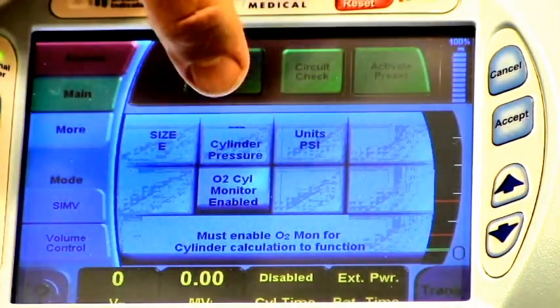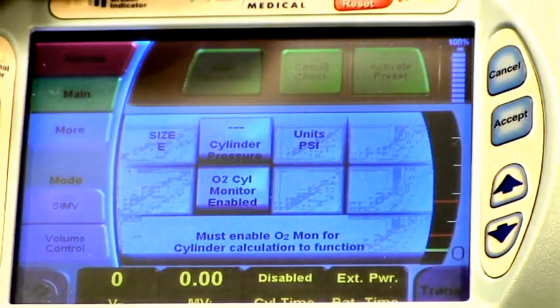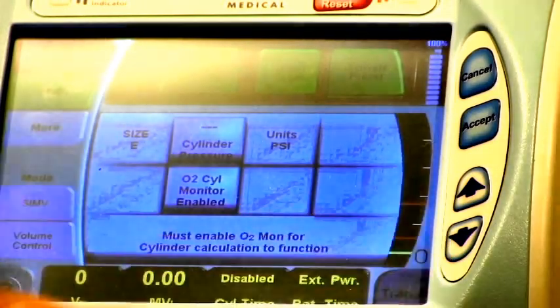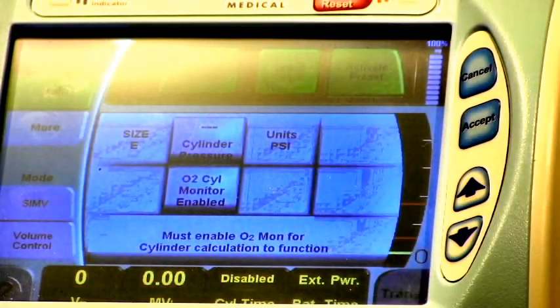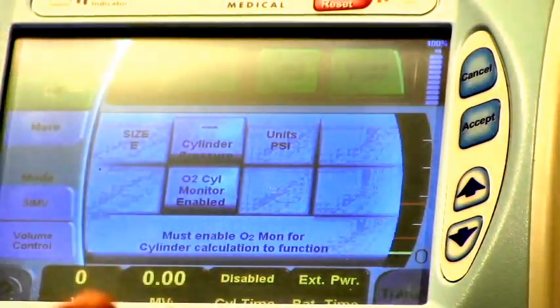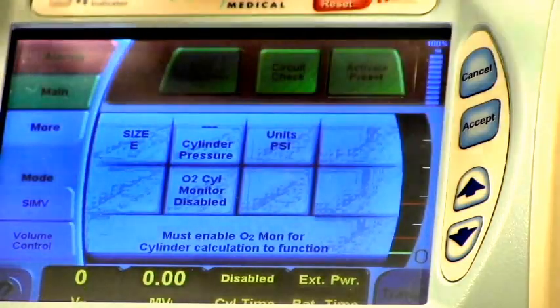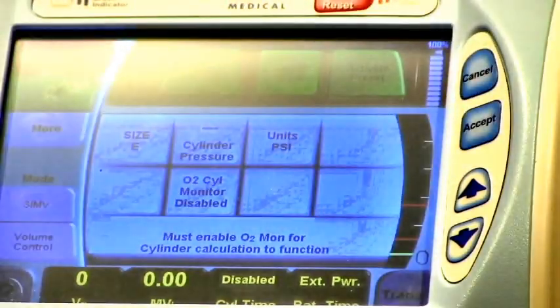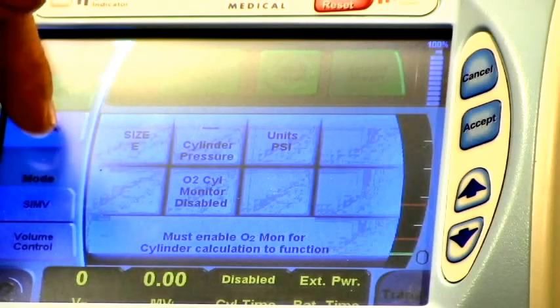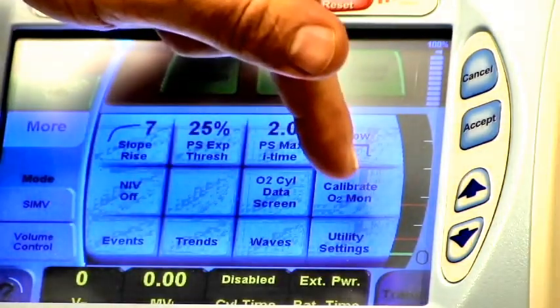The next thing we're going to do is add in our cylinder pressure. You're going to do this by your up and down arrow. Enter it in. I'm not going to enter any of it in now because I don't have a tank in here, and it's just going to yell at me if I put something in there. Once you're done with all that, again, you're going to hit accept. You're going to go back to the more screen, and then you're going to go to calibrate O2.